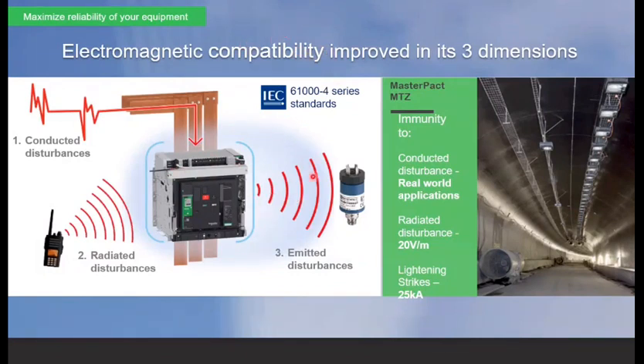So it has enhanced the immunity of your ACB against 3 types of EMC anomalies. First is conducted disturbance, second is radiated disturbance, and third is lightning strikes. You can see here on your page. So MTZ is complying to IEC 61000-4, which talks about these 3 types of EMC anomalies, and your MTZ is complying to all these 3 EMC anomalies. So MTZ is a robust breaker. You don't need to go for external EMC mitigating devices. Your breaker itself is sufficient to sustain in the environment.